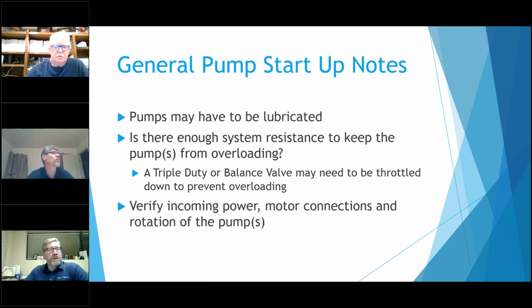But before you turn the pump on, you do want to make sure you verify your incoming motor and the power connections. Three-phase, you do want to make sure you're turning the pump the right way. There is an arrow on the pump showing what direction it should be spinning. You can push that to look at where the motor should be spinning. So you want to make sure it's going the right way. I've run into a few instances where it was running the wrong way. The pump will actually pump running the wrong way.